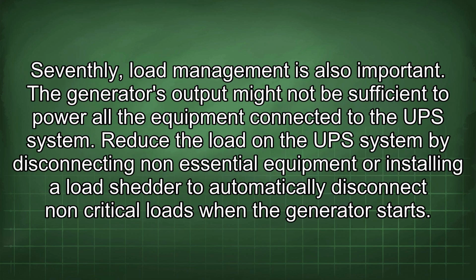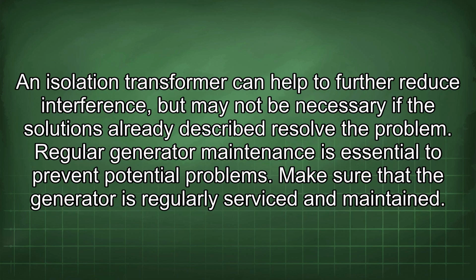Seventhly, load management is also important. The generator's output might not be sufficient to power all the equipment connected to the UPS system. Reduce the load on the UPS system by disconnecting non-essential equipment or installing a load shedder to automatically disconnect non-critical loads when the generator starts. An isolation transformer can help to further reduce interference, but may not be necessary if the solutions already described resolve the problem. Regular generator maintenance is essential to prevent potential problems. Make sure that the generator is regularly serviced and maintained.